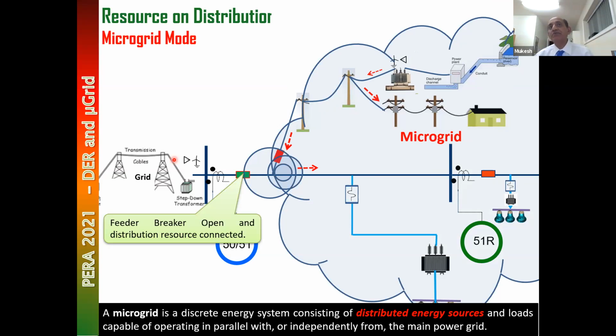Now, what are the benefits? One of the big benefits we are talking about is microgrid. Microgrid basically allows this resource to operate with this feeder with this breaker open. When this breaker is closed, the resource is operating in grid-connected mode, and with this breaker open, we are allowing the microgrid to operate. We are allowing this resource to serve this load customer while the grid supply is gone for some reason. So by using local generation, we are improving the reliability of the supply, not to mention reducing losses and better voltage regulation. But one of the big benefits is that if you lose grid electricity, you have a local source to supply your loads. So you have better grid reliability.